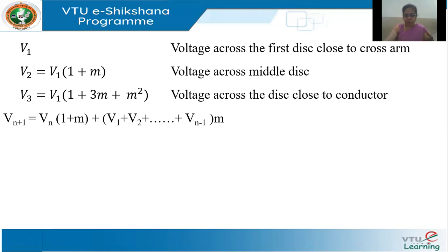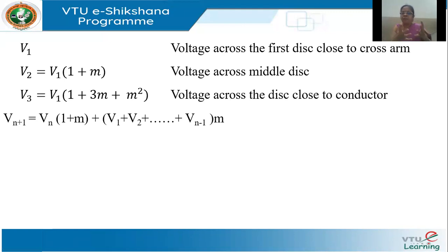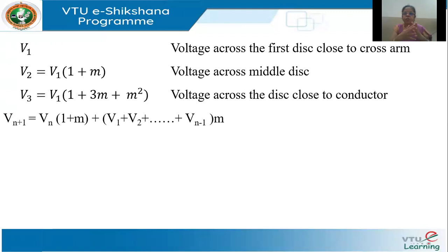For example, if you have 5 discs, then V5 = V4·(1 + m) + (V1 + V2 + V3)·m. If you have 7 discs, then V7 = V6·(1 + m) + (V1 + V2 + V3 + V4 + V5)·m. You can easily write the expression for any number of discs. From an examination point of view, you may be asked to solve for a maximum of 3 or 4 discs.